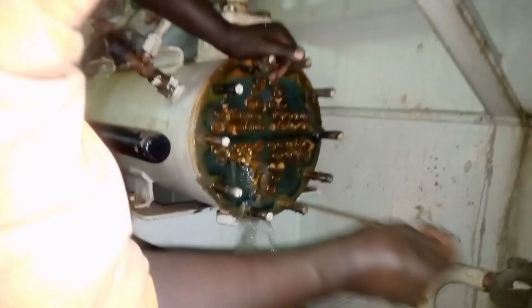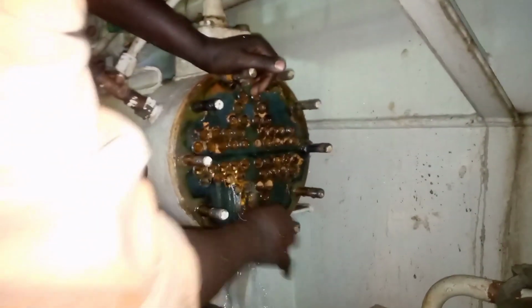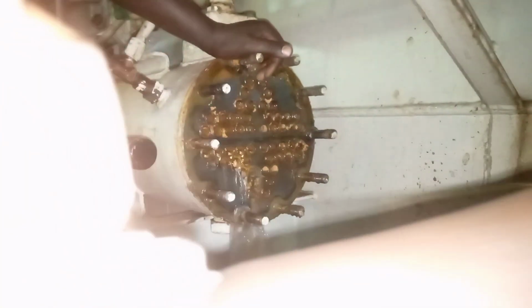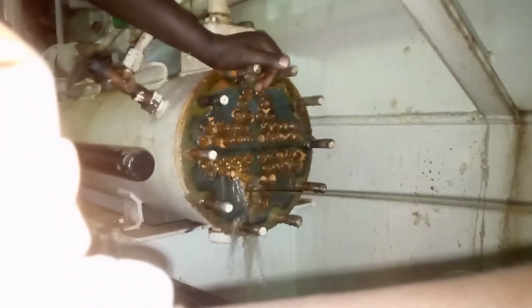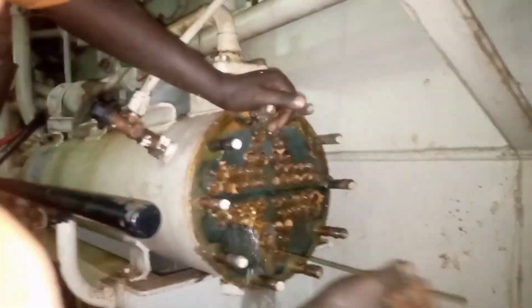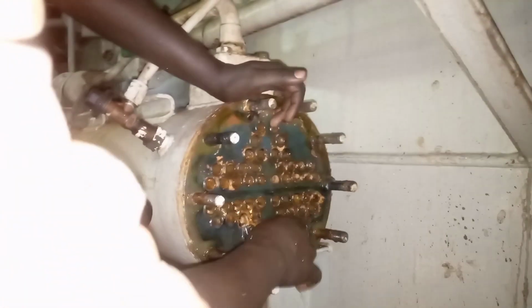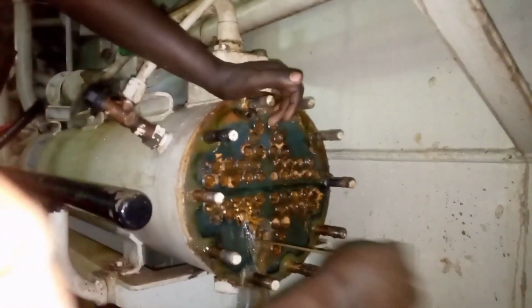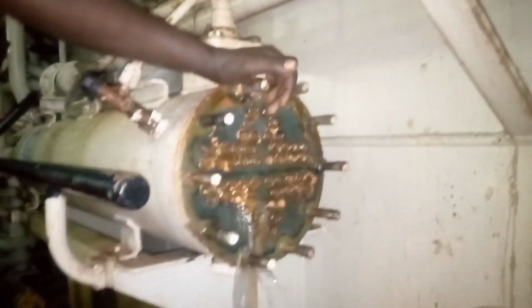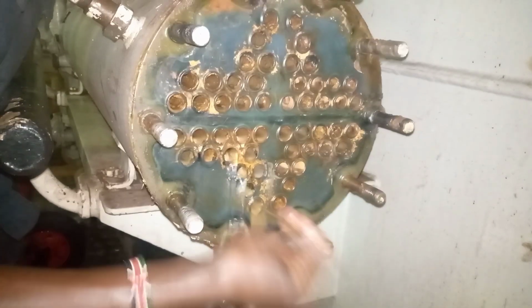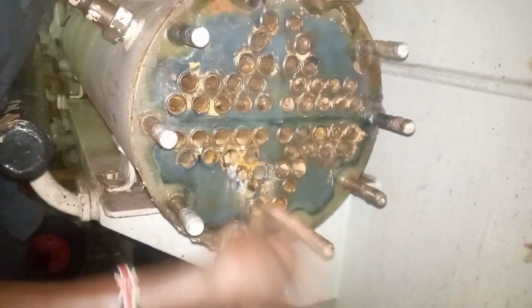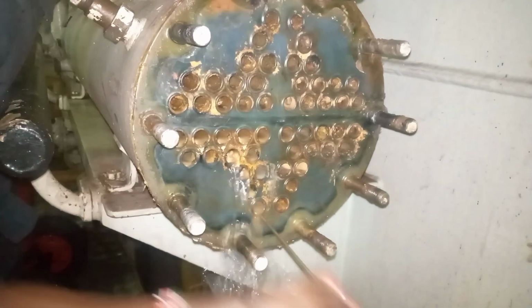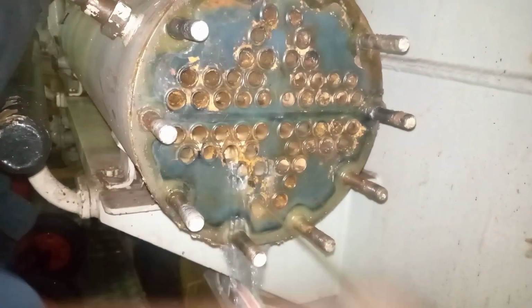After cleaning the end of the heat exchanger, it was now time to clean the inside of the heat exchanger tubes, and we used a wire that was long enough to scrub off the corrosion that was inside the tubes. And as you can see, it was easier, and as we scrubbed off, the corrosion was coming out.